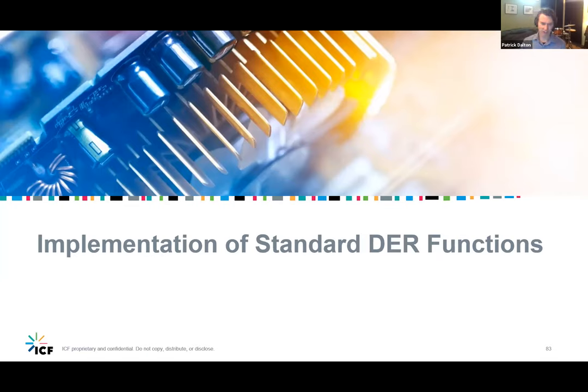My general sense in my experience has been that I just haven't seen very many harmonics issues with DER recently that isn't related to some sort of resonant harmonic condition on the system. So yeah, there's some level of harmonics maybe the DER is contributing, but it's really a resonant type of issue that maybe there's a capacitor bank.